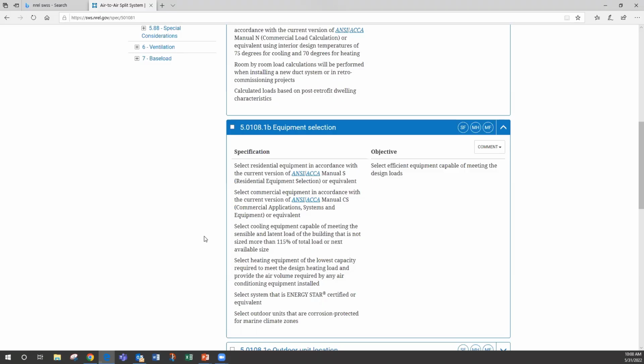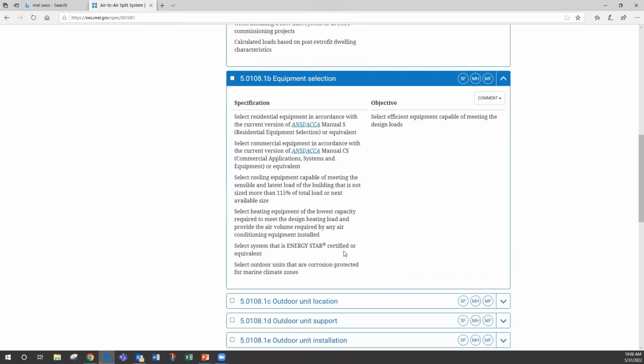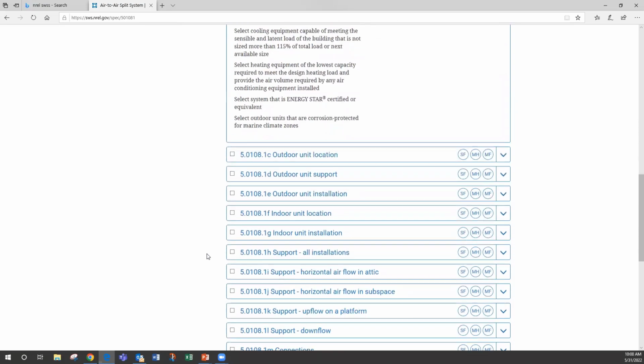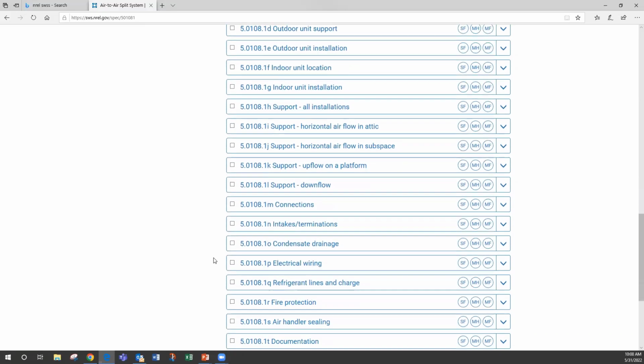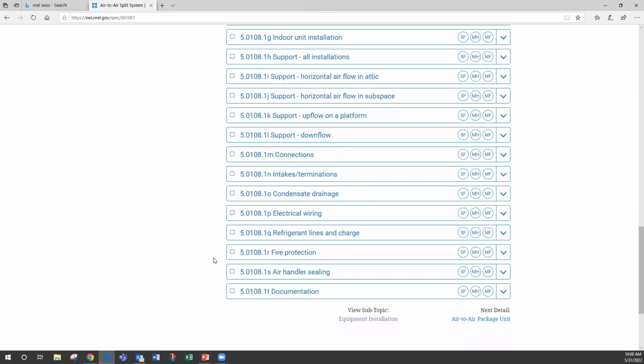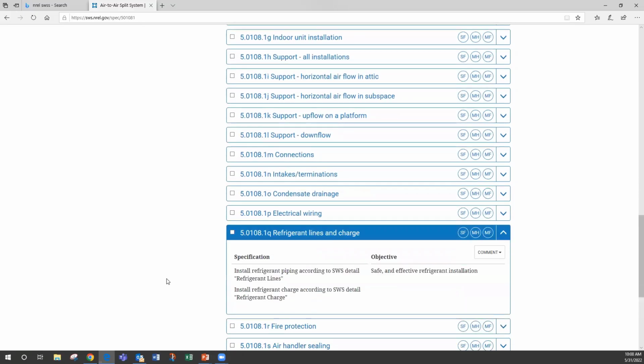Under equipment selection, they have a chart that shows the maximum you could oversize or undersize a system. So 115% would be your total max. Again, a system that is Energy Star certified or equivalent. And then the rest of it all pertains. It's just outdoor unit location, support, installation, etc. So if you get into a job, make sure you go into your SWSs. Let's take a look at refrigerant lines and charge.